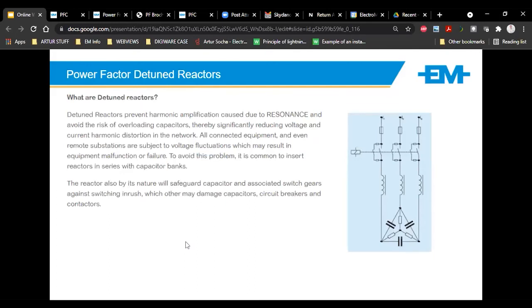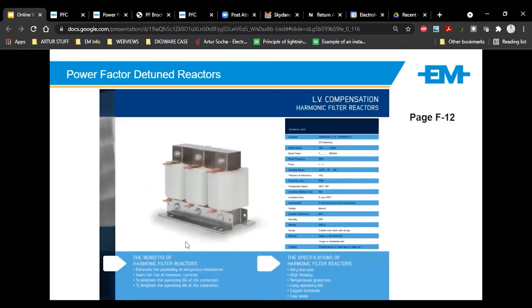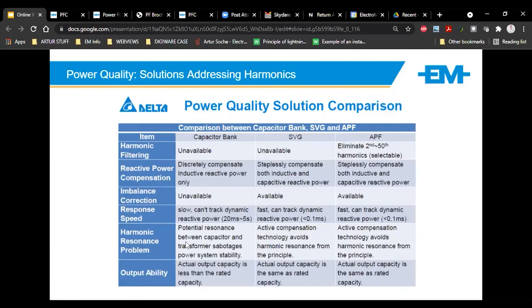We also do a full range of detuned reactors. What is a reactor? It looks like that, and it's wired in series with a capacitor. We've got a range from 400 volts to 550 volts, so we can design a system around those network conditions. Then for power factor, for power quality, we can do capacitor banks, but it is limited, slow response. We do what we call static VAR generators, which are dynamic. These will do power factor correction, leading and lagging, in less than 1 millisecond. And then what I mentioned earlier, active power filters, and those are specific to clean out harmonics on your grid.